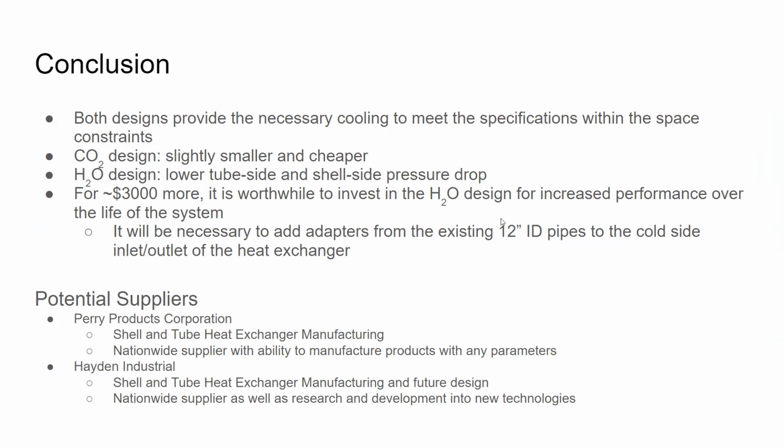In conclusion, we found the configurations of both cooling systems to meet the specifications given, finding that CO2 was slightly smaller and cheaper, but H2O with a significantly less pressure drop.